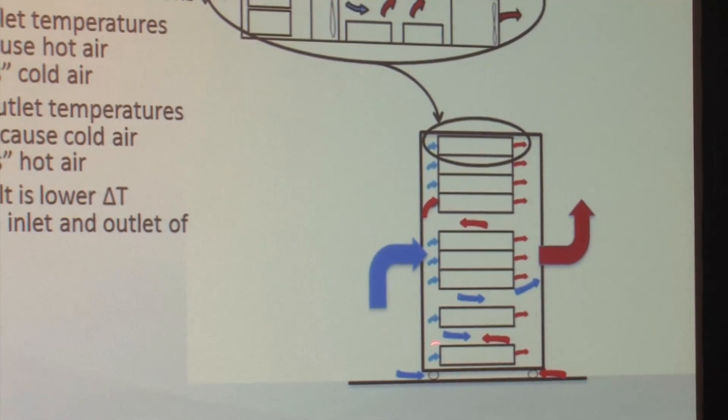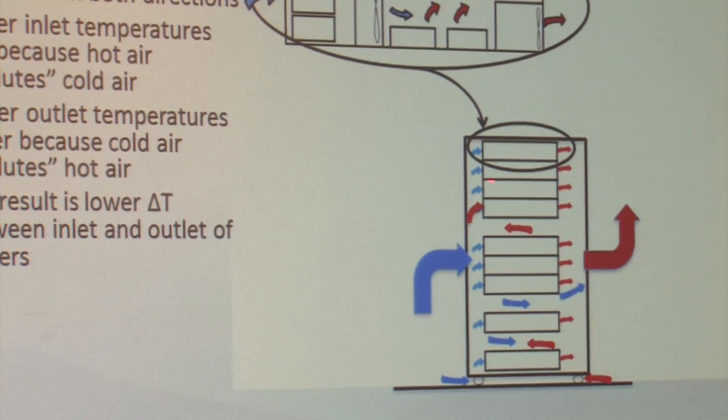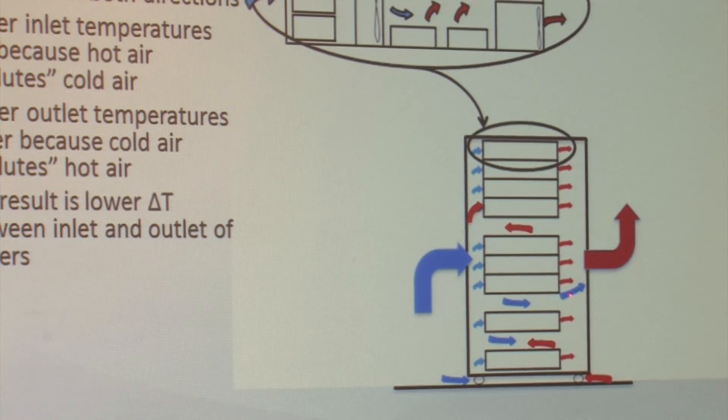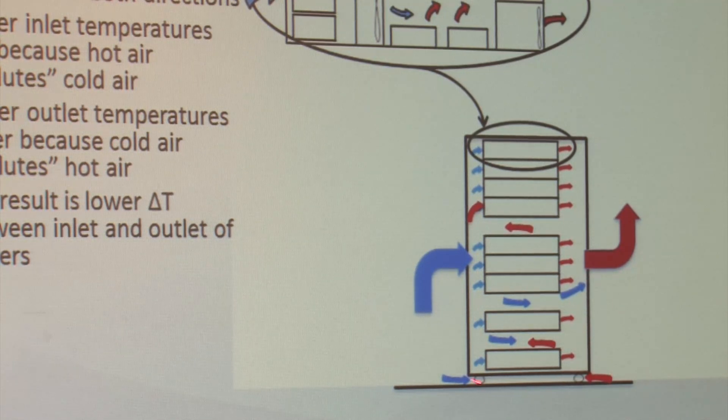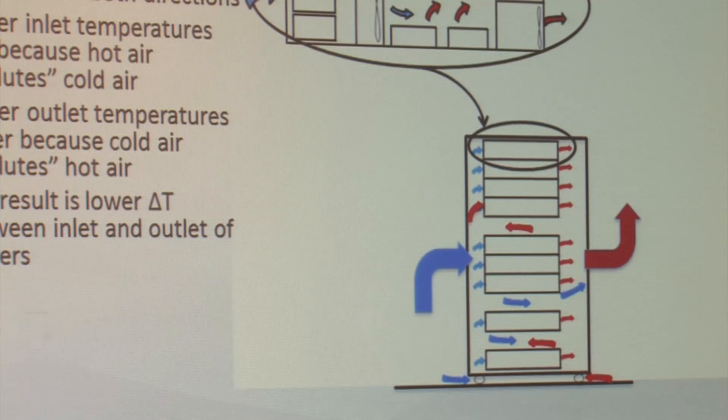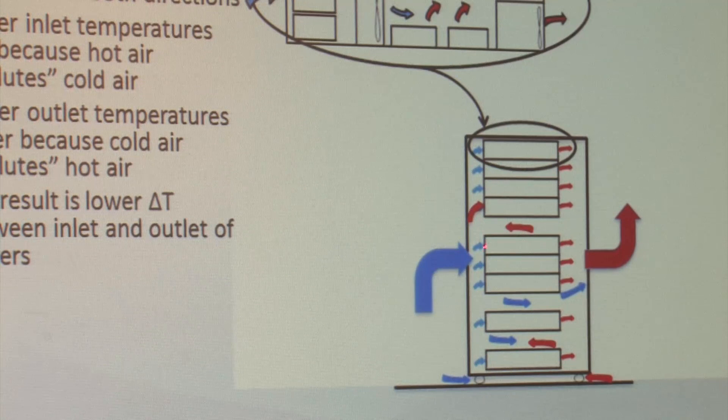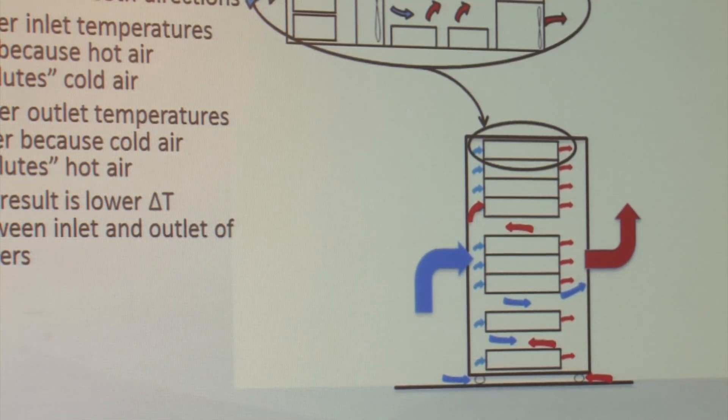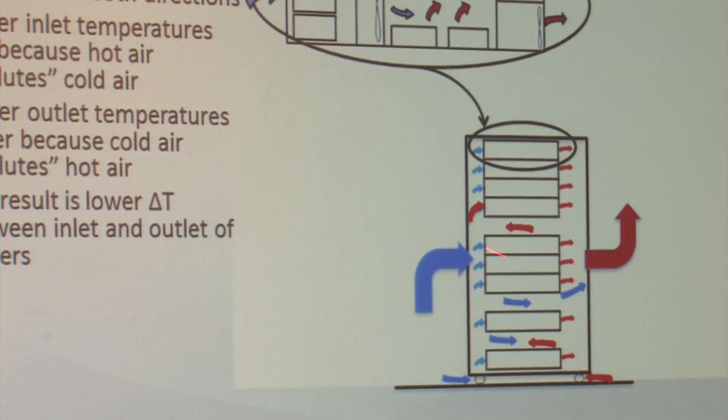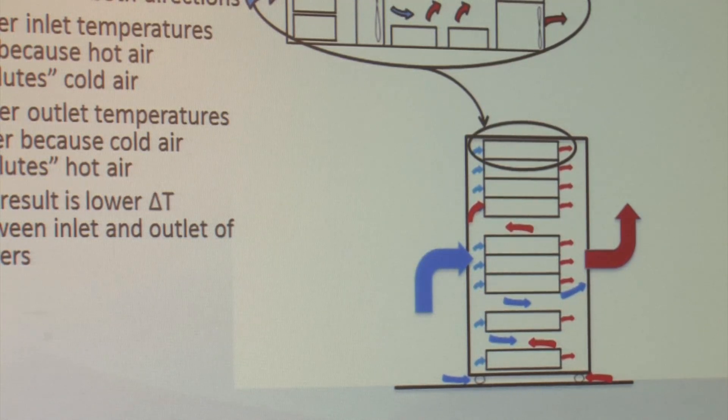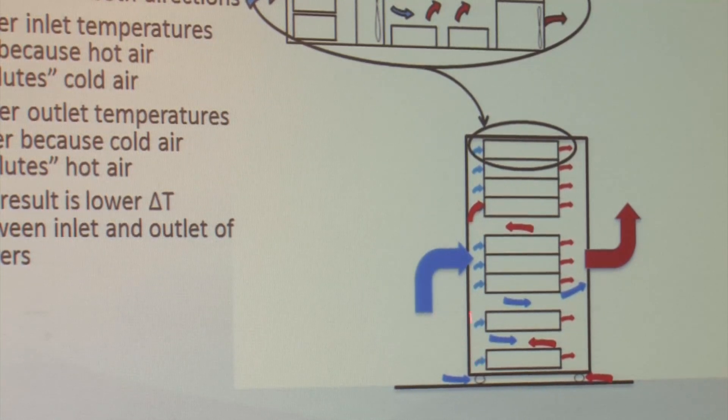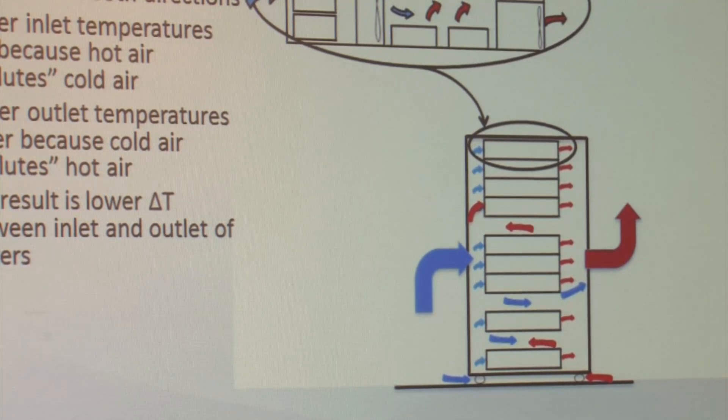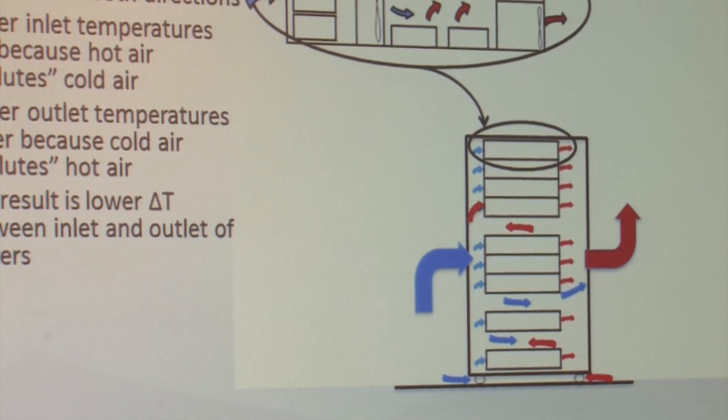And if everything is perfect, ideal, air at the same temperature will go into the servers. But you've got kind of recirculation here. You may have recirculation here. You even have recirculation coming under the floor sometimes. Or what you can't see in two dimensions is the recirculation between cabinets. So when you get this hot air that comes up here, it kind of pollutes this cool air. And usually, the higher you get, the more of that hot stuff gets up into the top of the cabinet. So you may have this temperature down here that is probably pretty close to the supply temperature from the air handler. And this is probably considerably higher.